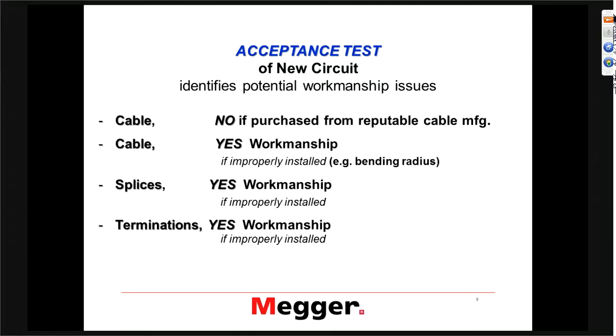But we are concerned about the cable from a workmanship issue — for instance, bending radii or pulling force on cables, which can affect the cable itself. Then we look at splices, which is a workmanship issue if improperly installed, or maybe there were some compromises done to install a splice. And the same is true for terminations.